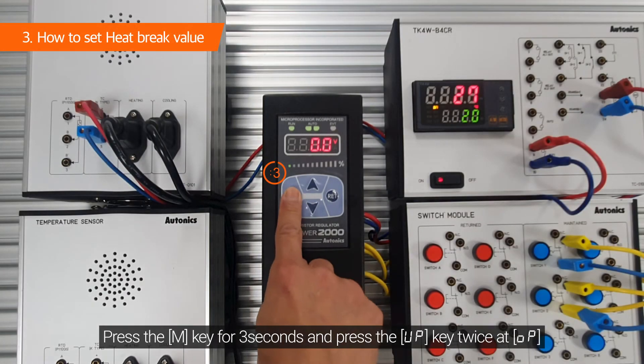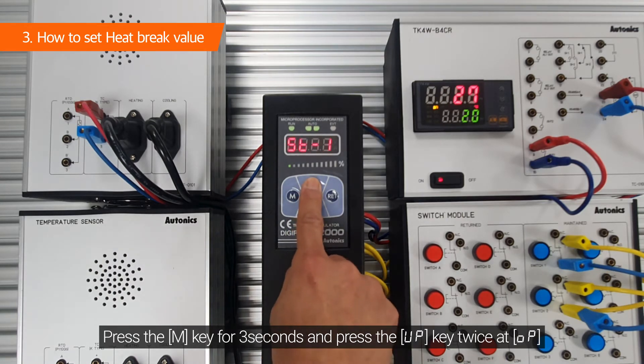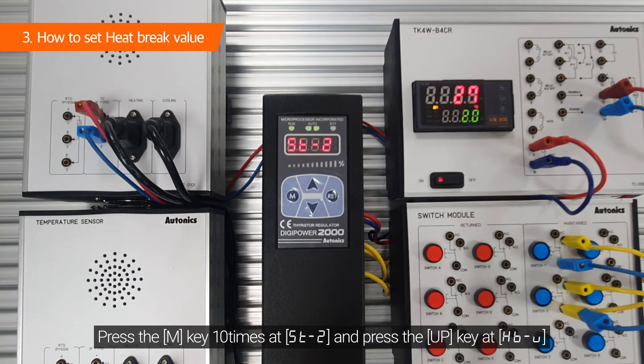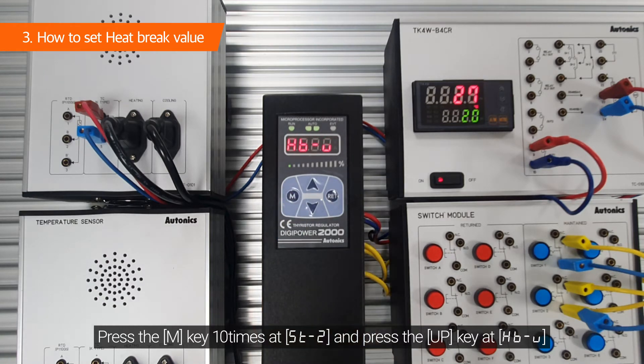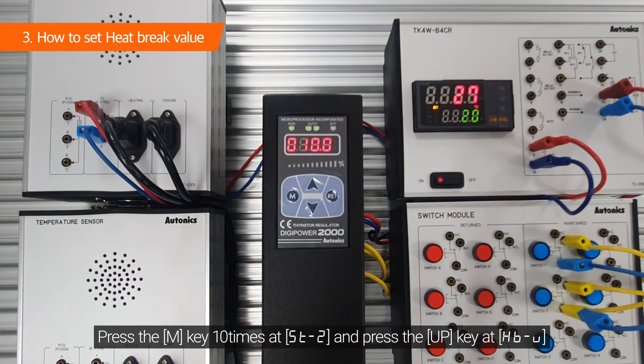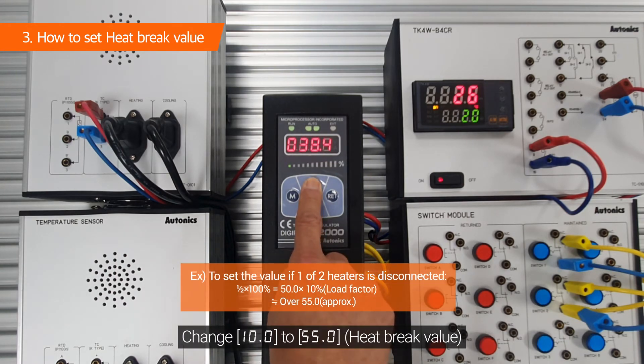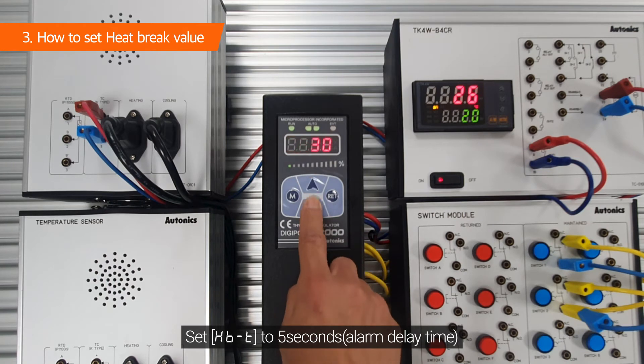Press the M key for three seconds and press the up key twice at OP. Press the M key ten times at ST-2 and press the up key at HB-U. Change 10.0 to 55.0. Set HB-T to five seconds.